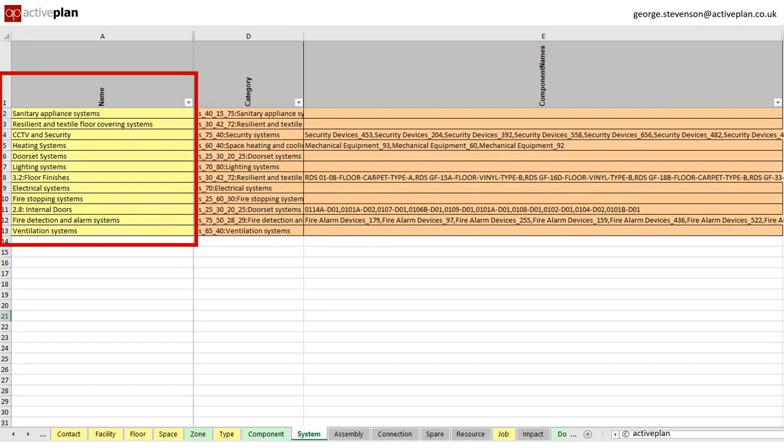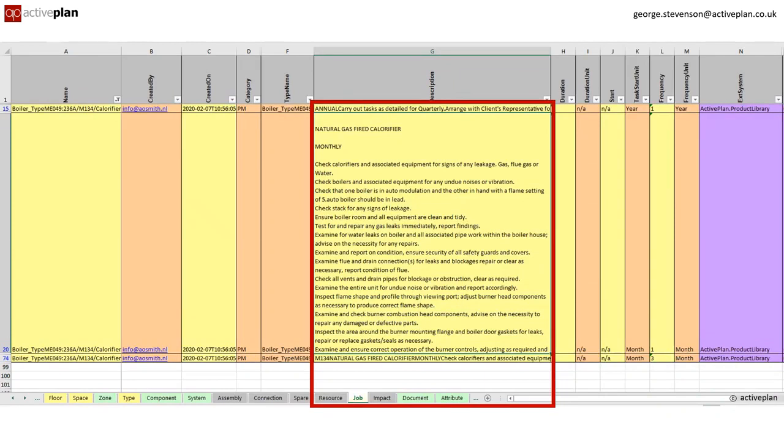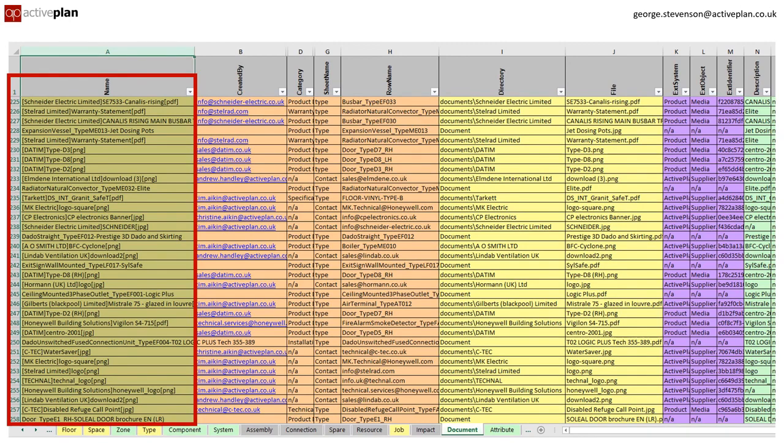The manufacturer's recommended maintenance regimes is included in the jobs tab, including the individual tasks that can be compared with the generic maintenance libraries like SFG20 to ensure nothing important for the warranty is missed. PDFs of manufacturer's manuals and test certificates are held under documents.